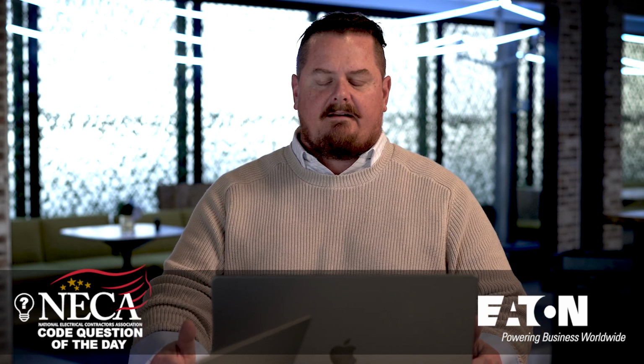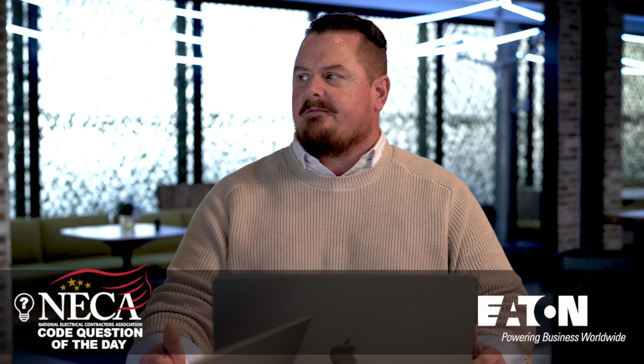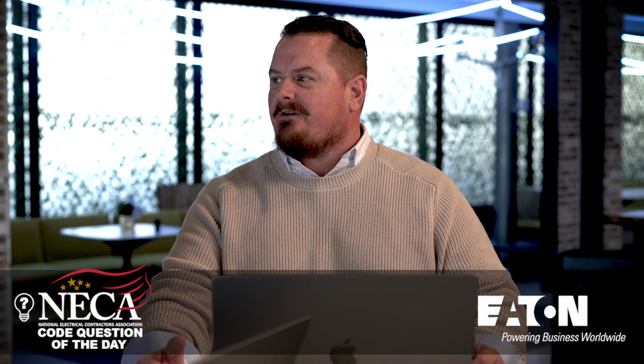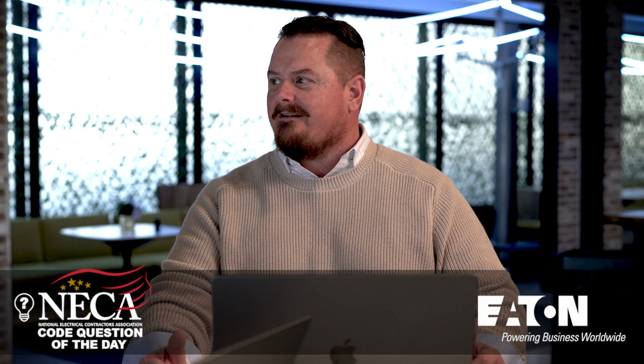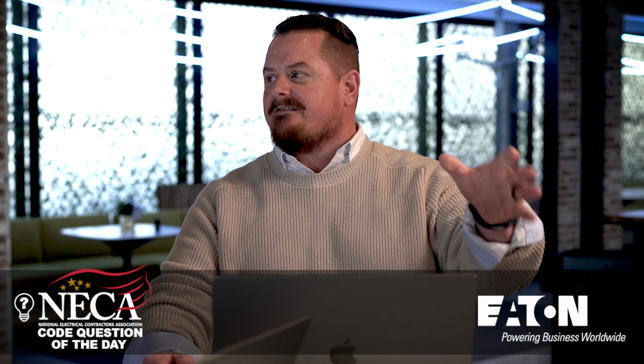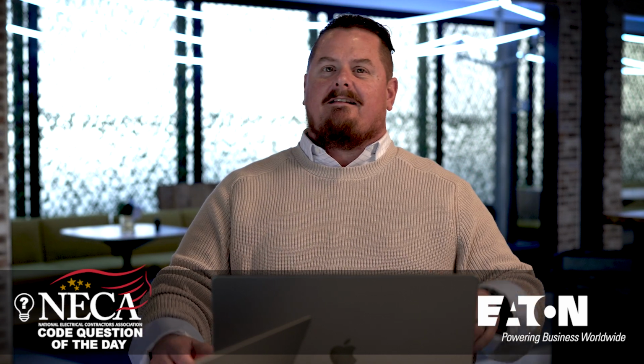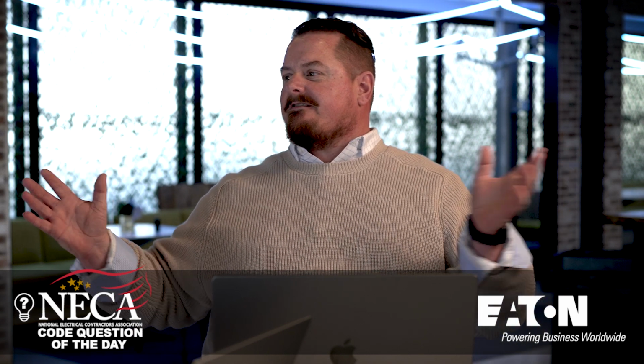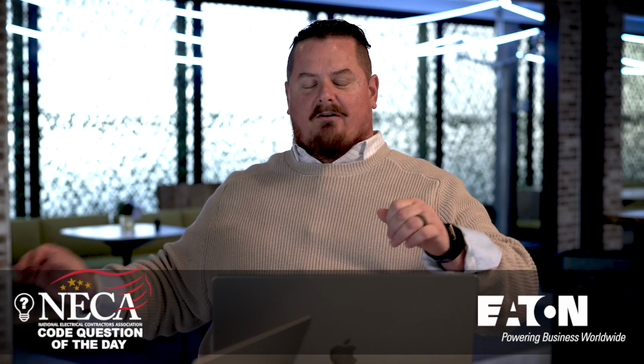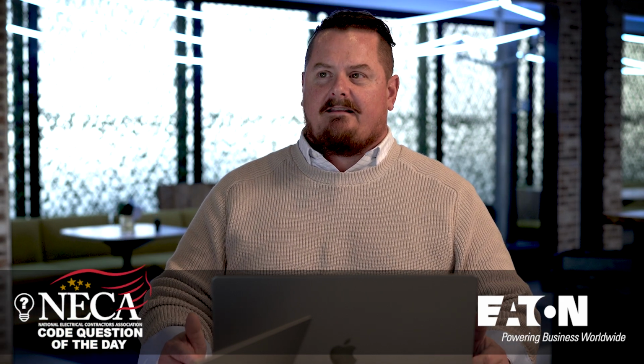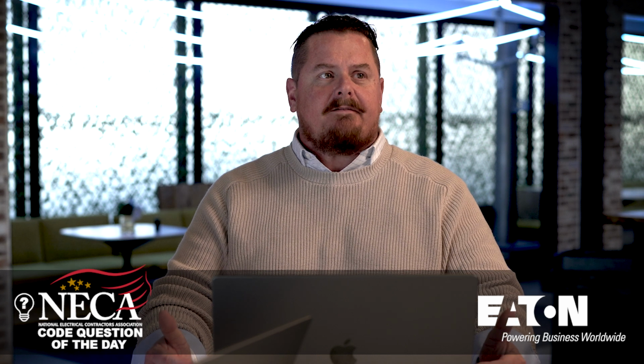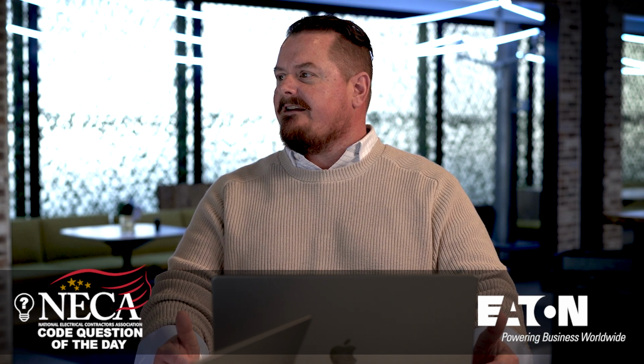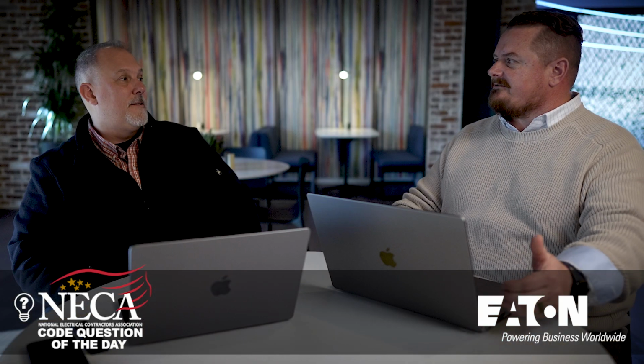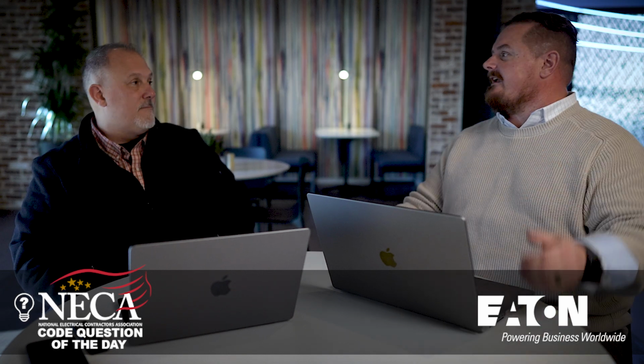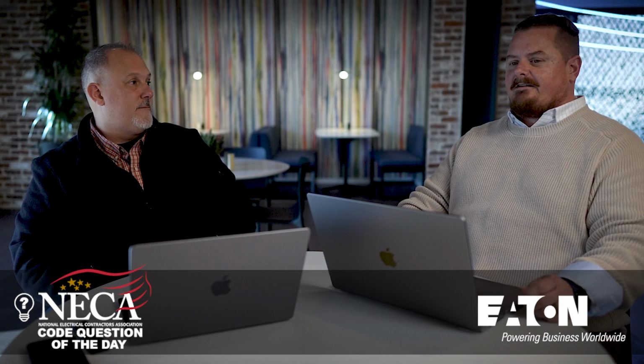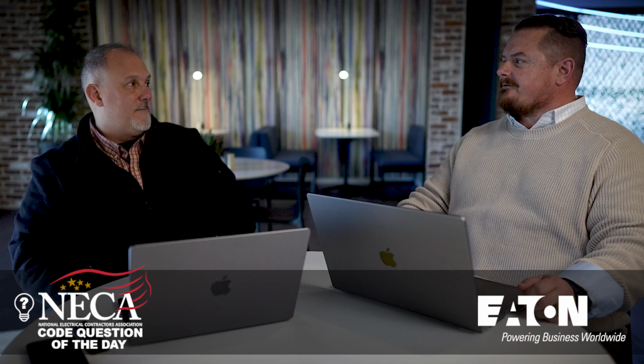there used to be, in my experience, this misnomer out there that as long as the service equipment was rated properly for the incoming fault current from the utility and the service disconnect was rated properly, like magically the available fault current just disappeared after the service disconnect and all was good. So it seriously feels like it's been a 15-year effort in trying to retrain not just installers, contractors, engineers, but also AHJs.